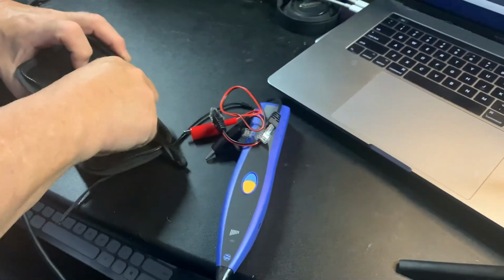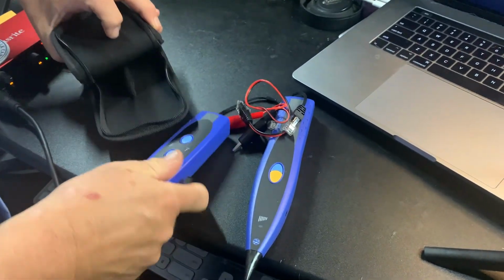Now let's look at each component separately, starting with the probe. The probe comes with a replaceable, non-metallic tip, and I like that it's non-metallic, because I've used probes in the past with metallic tips that shorted out equipment — shorted out connectors on terminals and caused problems. So I like that it's non-metallic, especially with what's right behind that tip.